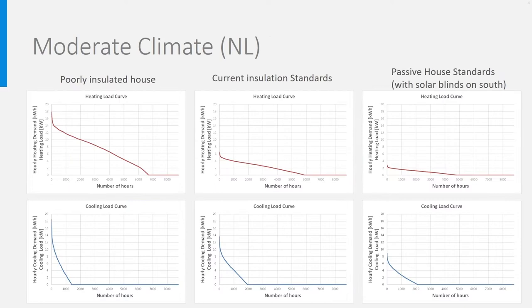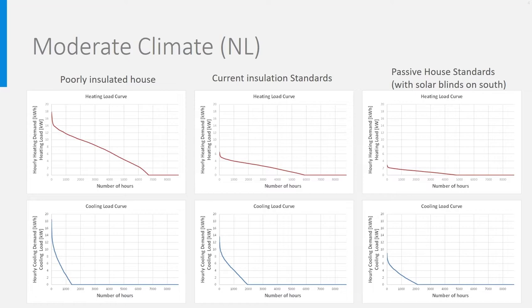You see here the load duration curves for heating and cooling over one year. On the left for a poorly insulated version of the house, typical for the building stock built before 1970. In the middle for a house insulated to current standards, with a highly insulated roof with RC value of 6 square meter Kelvin per watt and good insulation of walls and floor around 4. On the right it is for an extremely well insulated house according to passive house standards, with RC value around 8, solar blinds on the south facade, and ventilation with heat recovery.